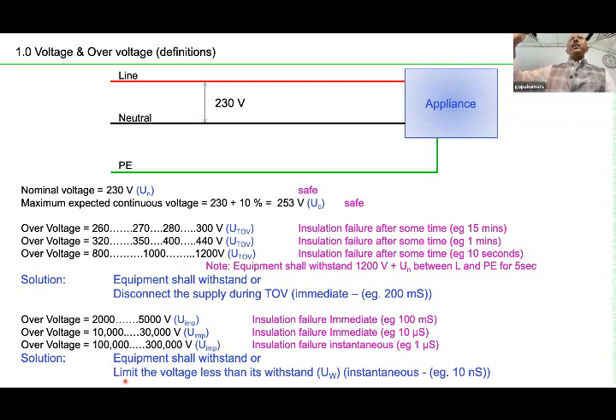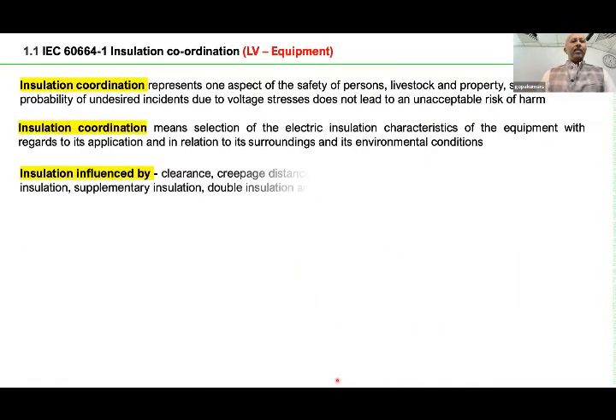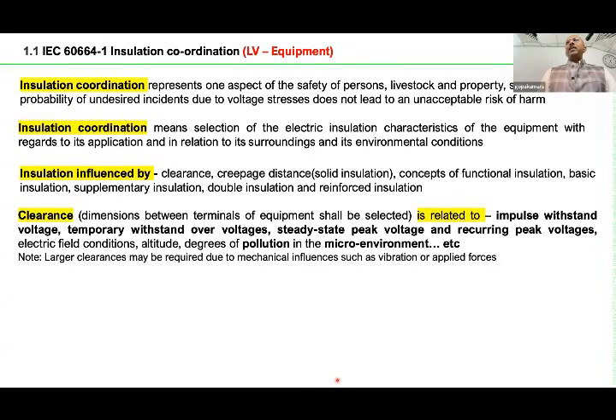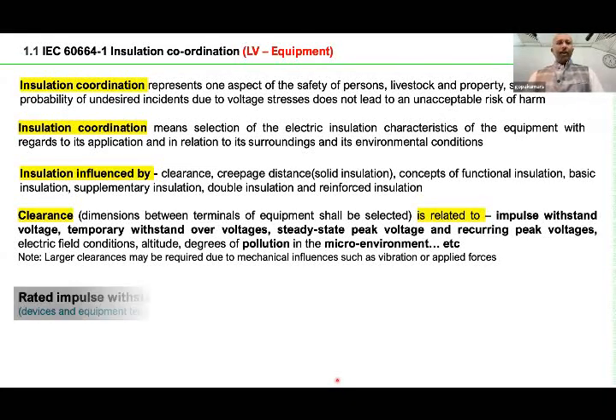Let's say 30 kV is the voltage coming to the equipment because of lightning activity. You cannot switch off your equipment, because switching off will take a few milliseconds. You have to sense it and switch it. Before that, the voltage comes, destroys the equipment and goes back. So what should you do? You should put in some device and ensure that this 30,000 volt is reduced to a limit equal to the insulation withstanding level of this particular equipment. So the impulse withstanding capability. The first point of surge protection is what we mean by the insulation withstanding level of an equipment. So we should look at insulation coordination.